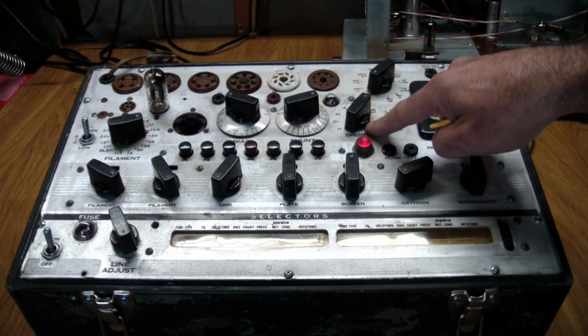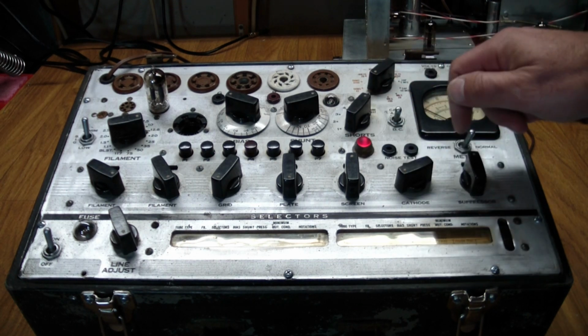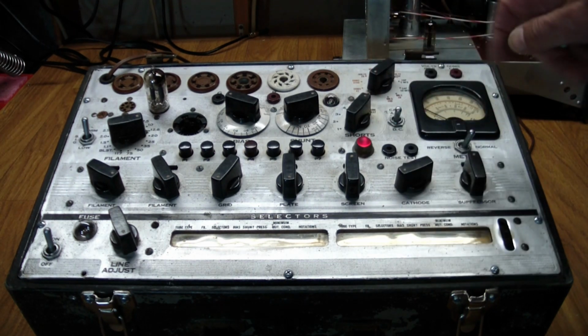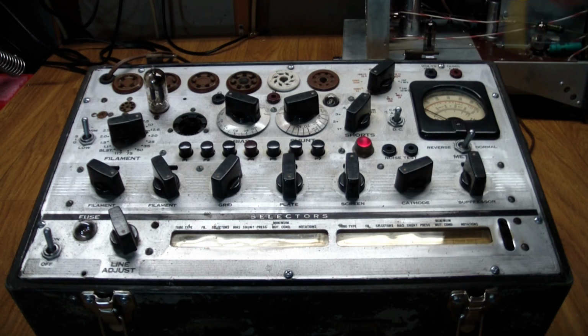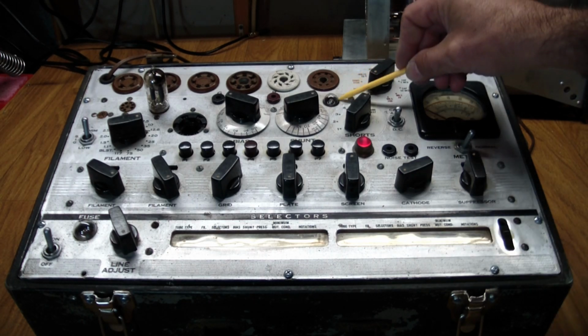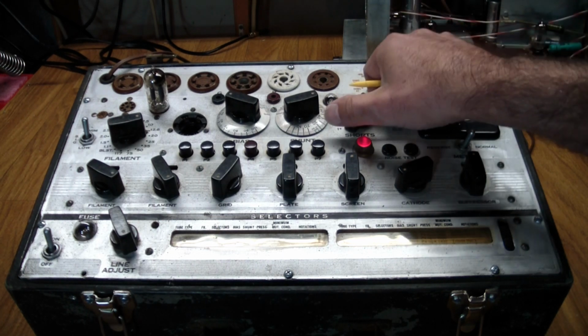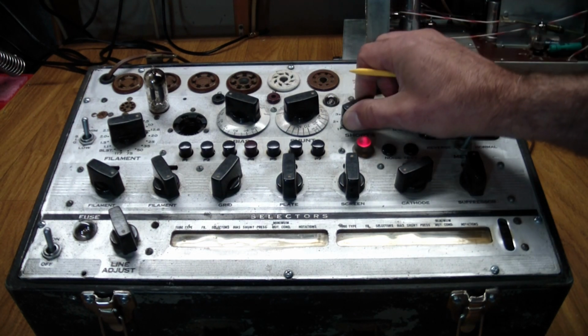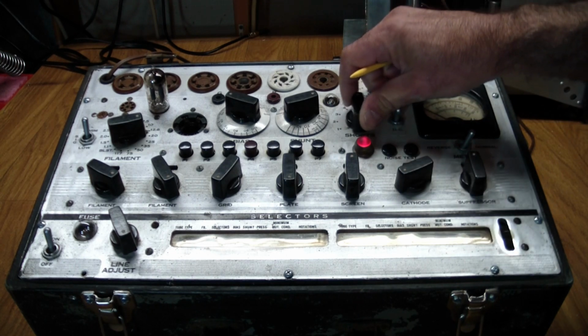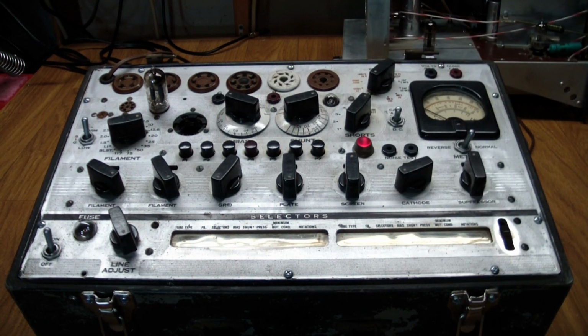You have this dial that goes from 1 to 5 and then to tube test, and if you turn it to any position from 1 to 5, it checks pin shorts, and this will light up brightly. You saw it flash maybe, and that is actually normal. It may flash when you're initially turning it, and that's not a problem, but if it comes on and stays on permanently, then you've got a problem. So there's no short in the tube, and everything is set up as the entry in the table showed us.